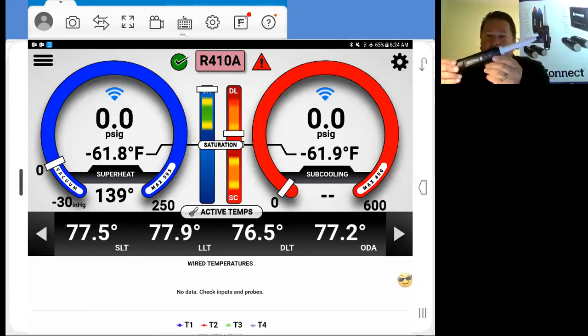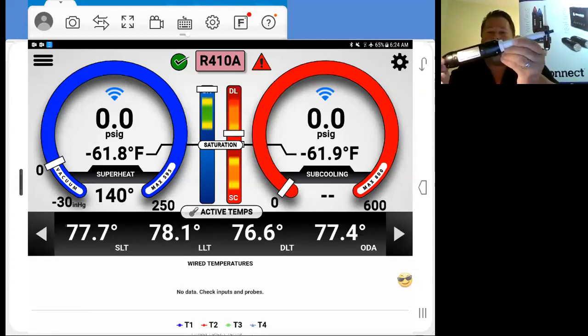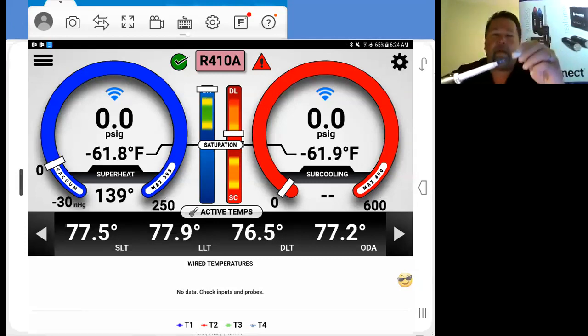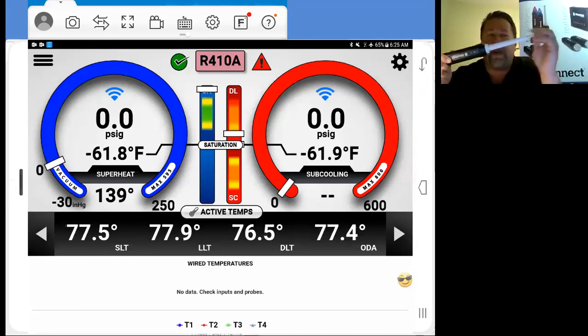But as you can see on the switch side, basically the front of the probe, there's nothing on the end here. The sensor itself is actually along the back side. You see this little black box over here, that's the actual sensor tip. And that's on the side where the battery cover is. So just keep that in mind when you're getting this into the flow of air, that airflow does come over this sensor tip on which side, because if you've got strong airflow going at it face-wise, it's probably not going to give you any airflow across the tip. Either kick it sideways or turn it around. Make sure you get airflow over the tip of this.